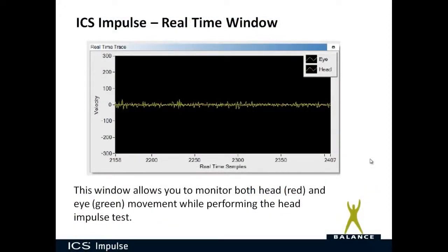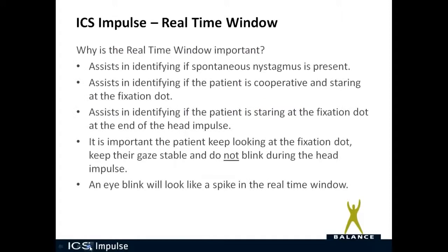When you're doing your head impulse, make sure you're looking at the real-time window. This window allows you to monitor both head in red and eye in green while performing the head impulse test. The real-time window assists in identifying if spontaneous nystagmus is present, if the patient is cooperative and staring at the fixation dot — if they're looking around, the green line will not be smooth — and if the patient is maintaining fixation at the end of the head impulse. It is important the patient keep looking at the fixation dot, keep their gaze stable, and not blink. An eye blink will look like a spike in the real-time trace window.